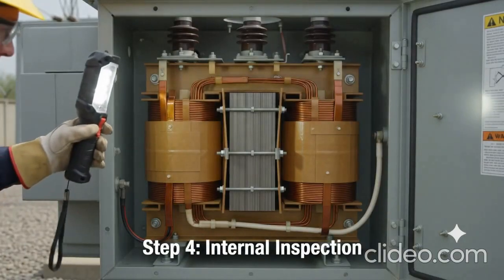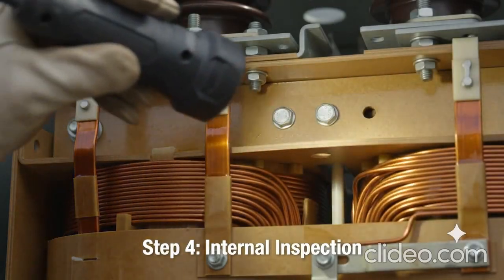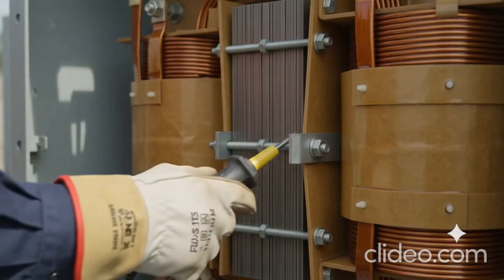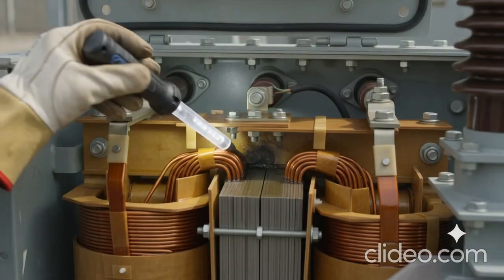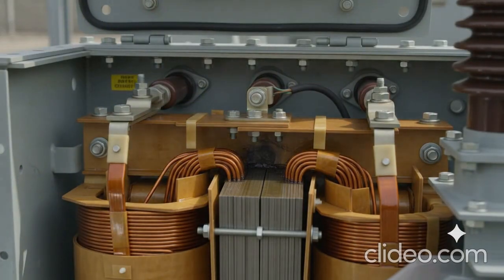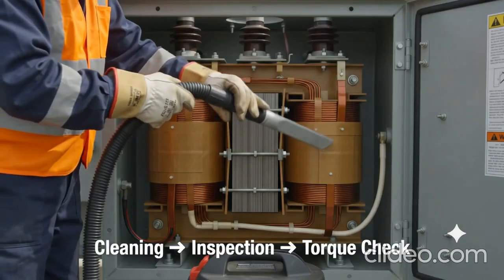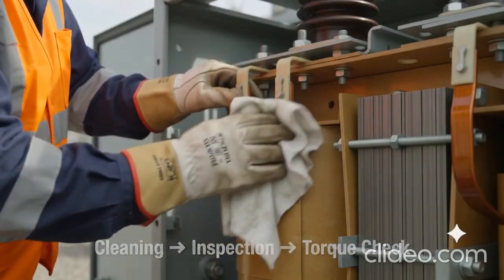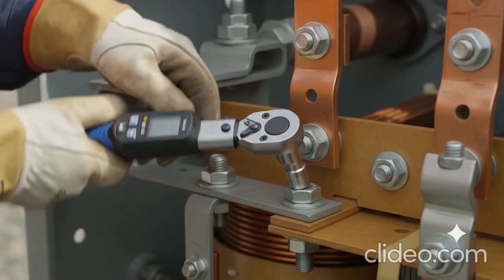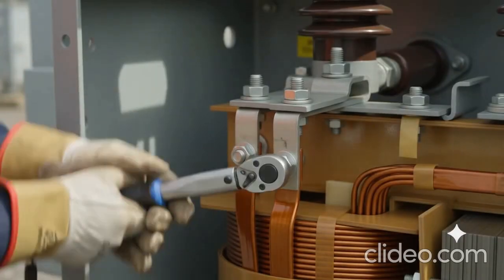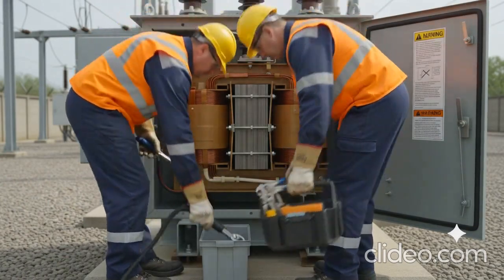The internal components are visually inspected for signs of overheating. We check for insulation deterioration, loose connections, and carbon deposits. Moisture, corrosion, or mechanical damage are also assessed. Accessible components are cleaned using approved methods. Electrical and mechanical connections are inspected and tightened according to the manufacturer's specifications.